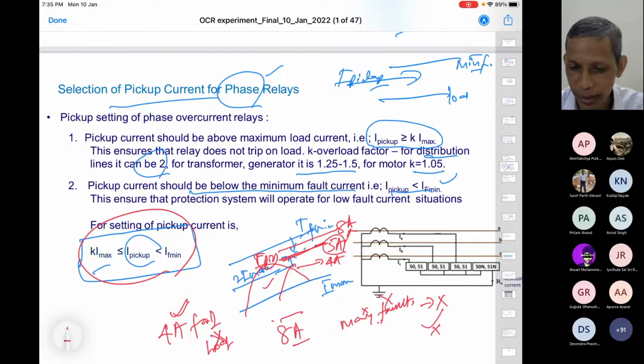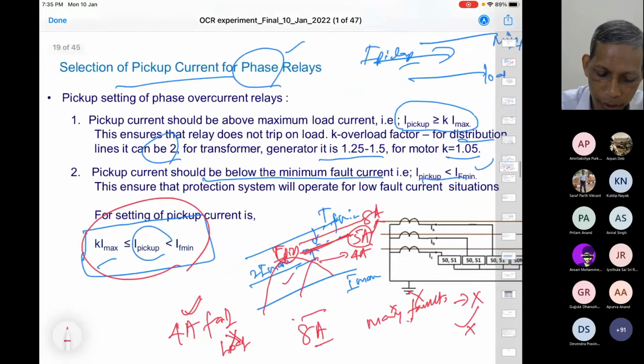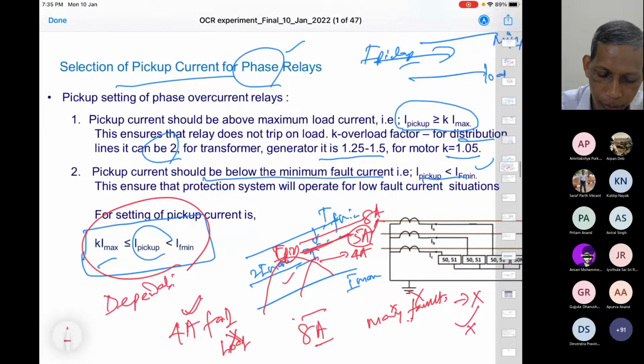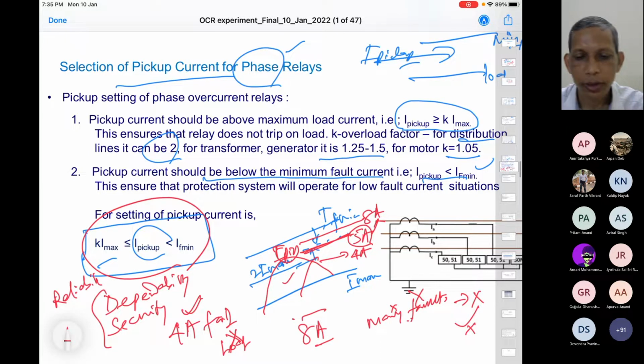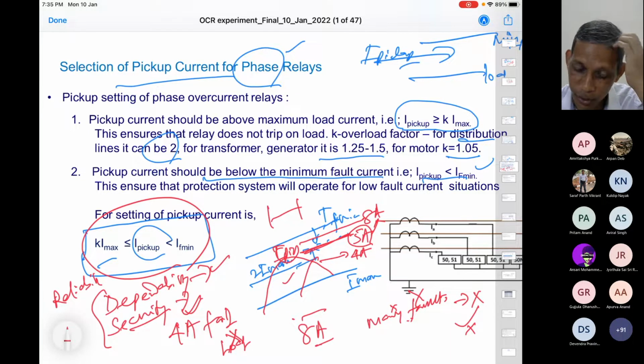So we call two terminologies in the design. This is called dependability, and we call the other security. And commonly considered is the reliability of the protection system or the relay. Now, what is dependability? The relay depends. What is the purpose of the relay? Fault, protect it. Go for tripping. That is about dependability. Security: no fault, remain silent. No fault where? In the assigned zone, in this line section only. It doesn't bother about other line sections or the transformer. That is about security.